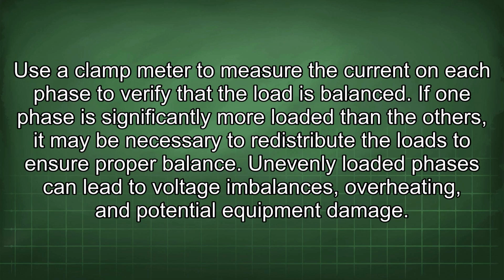Use a clamp meter to measure the current on each phase to verify that the load is balanced. If one phase is significantly more loaded than the others, it may be necessary to redistribute the loads to ensure proper balance. Unevenly loaded phases can lead to voltage imbalances, overheating, and potential equipment damage.